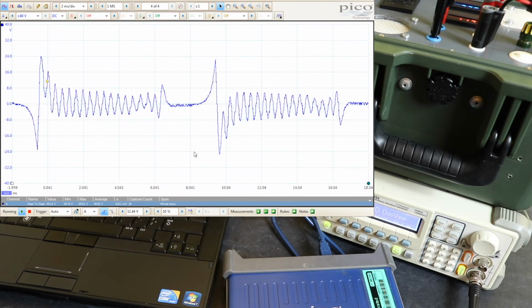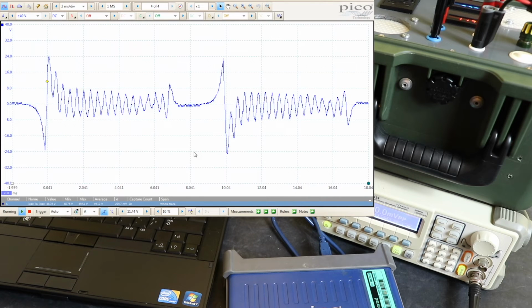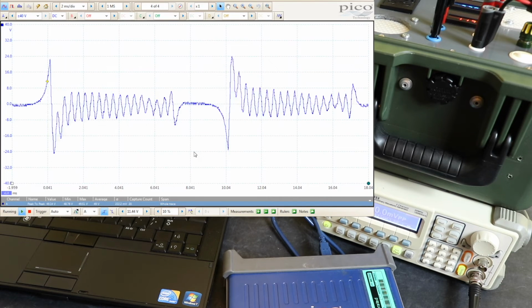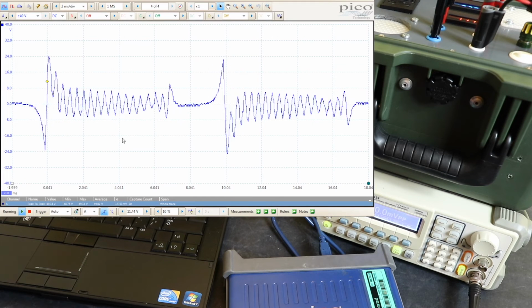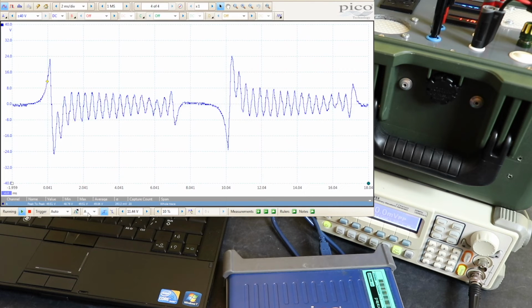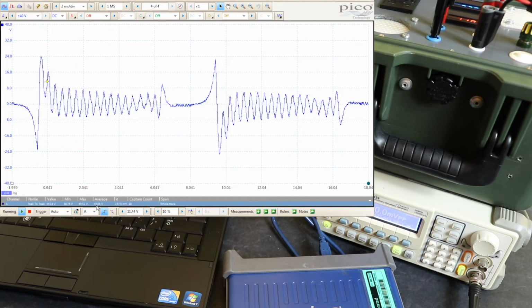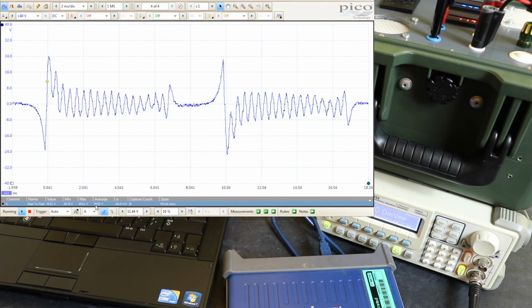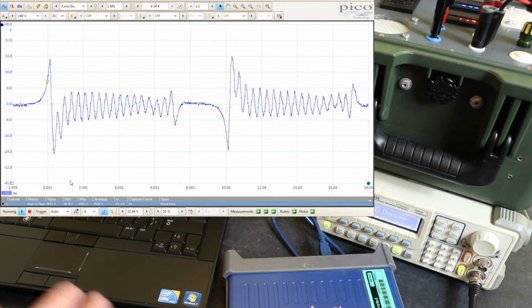I do have a proper AGSC, air gap search coil, or flux probe some people call them. I do have a proper analyzer for it, but that applies a load of filters and you don't get this raw data out that you can see in here. So this is why I like to capture it with the Picoscope. And you can see I've got a voltage measurement down there for around about 49 volts is averaging out, so I can record that, and that all seems to be working fine.